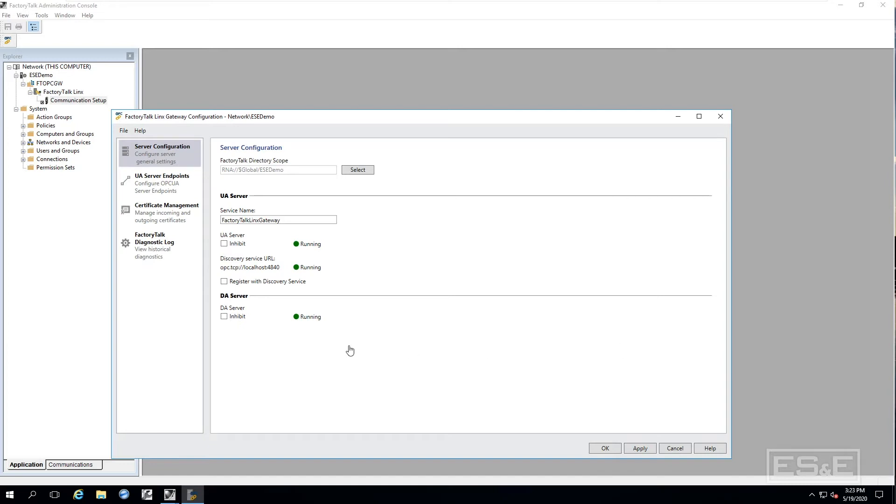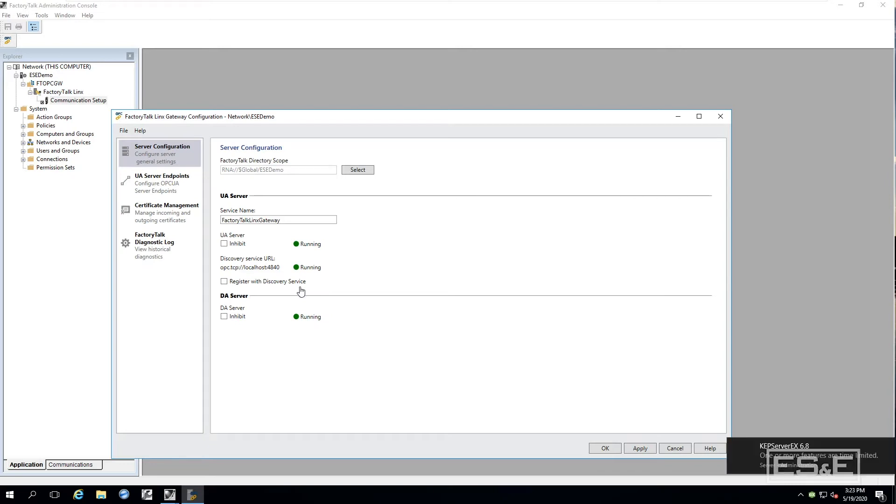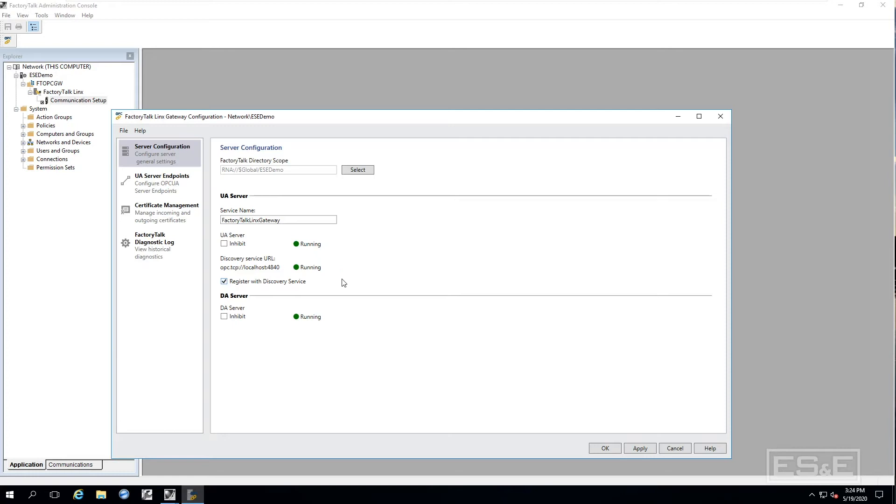The Register with Discovery Service. This is an option under the UA service that will register the FactoryTalk Linx Gateway UA server with the OPC UA local discovery server. This will allow an OPC UA client to browse to the FactoryTalk Linx Gateway server. So it is going to enable us to browse it and find it instead of us having to go in and actually type it out. So we are going to select it and register it with the Discovery Service.